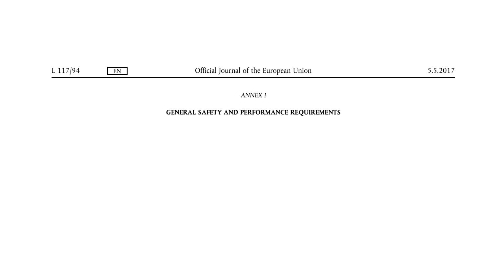Annex I in both the MDR and the IVDR comprises several pages of requirements that are mandatory to fulfill, if the requirement is applicable to the medical device in question. These requirements are called General Safety and Performance Requirements, often referred to as GSPR. Requirements related to manufacturing of medical devices are covered in several of the GSPRs. I will not mention all of them here, but I would like to draw your attention to a few key points.